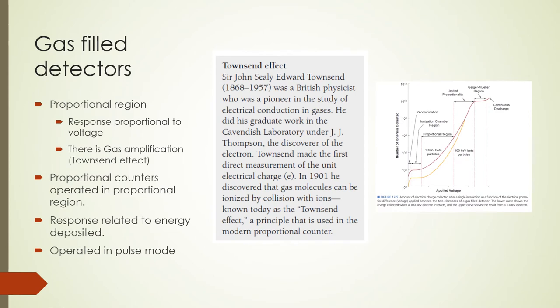The next region after the ion chamber region is the proportional region. As the voltage is increased past the ion chamber region, the response begins to increase with voltage, and we enter the proportional region — the nearly straight-line region where response is proportional to both the voltage and to the energy deposited. In this region, ions have enough energy to cause additional ionizations in a phenomenon called gas amplification or the Townsend effect. The amount of amplification increases as the voltage is increased. Proportional counters are usually operated in the proportional region in pulse mode and can be used as counters or spectrometers.